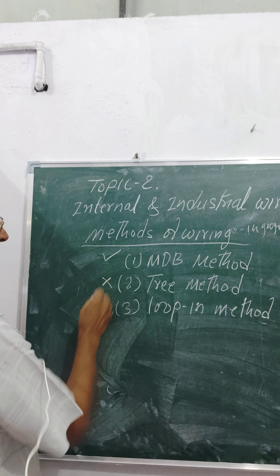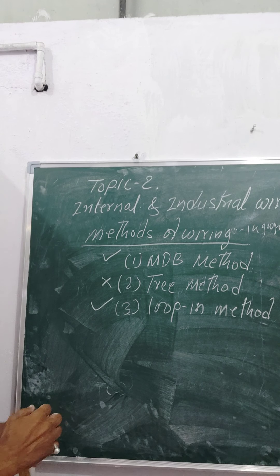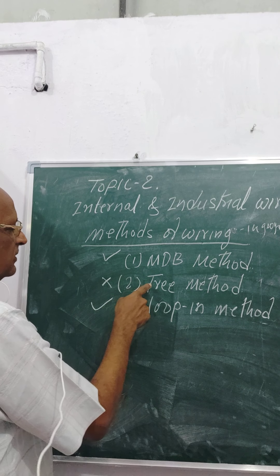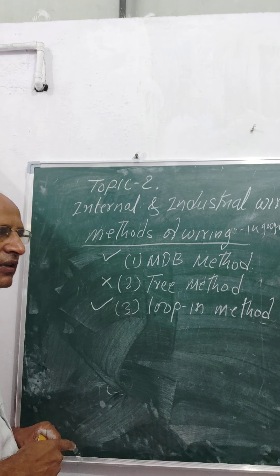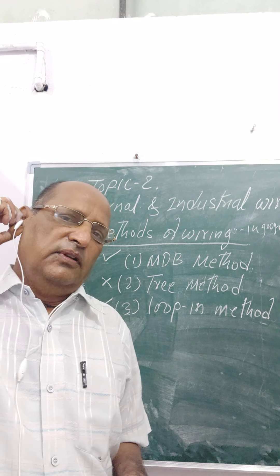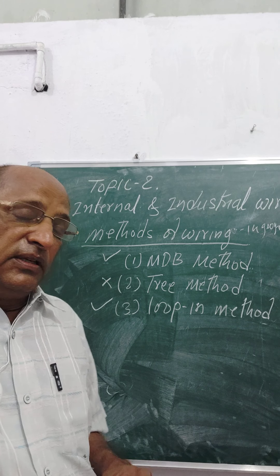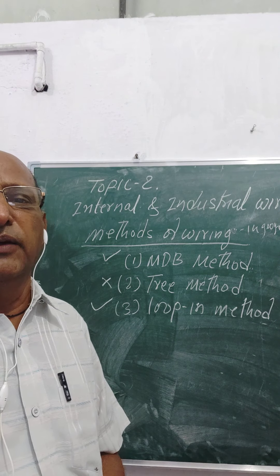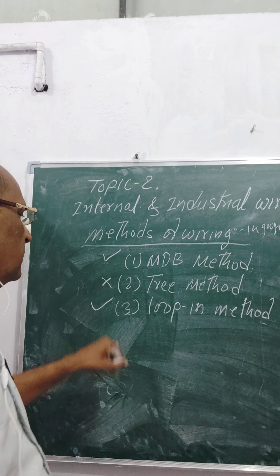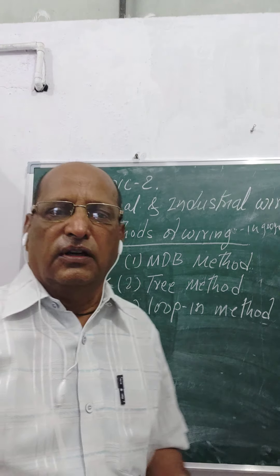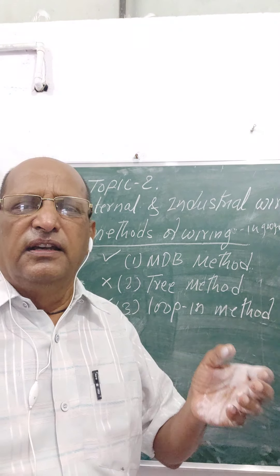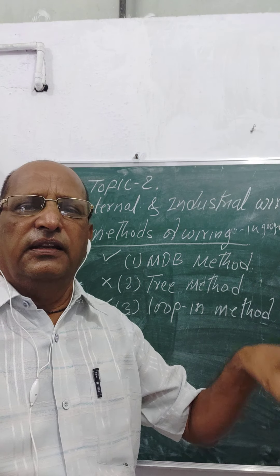The tree method is not preferred, while the MDB method is preferred. The loop-in method can be used with both MDB and tree methods, but the tree method has a key disadvantage: it has one single control for all circuits, so if a fault occurs in any one circuit, the whole system goes off. In the MDB system, every circuit has its own MCB or cutout for individual control.